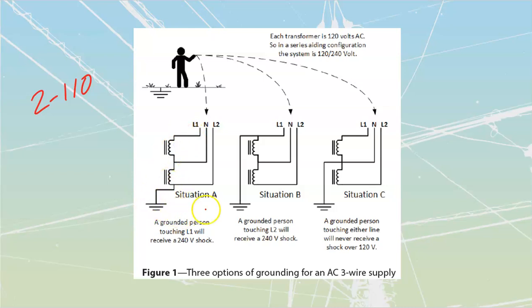So where we would ground the system would make a difference. This one over here, we would see that line 2 would be at 0 volts. They could touch line 2 safely, but if they touched the neutral, that would be 120 volts above it. If they touched line 1, that would be 240 volts above it. So there's danger over there, right? That 240 volt shock. Same with this one. If we grounded the other line, we would be able to get 240 off of that line, just standing still with our human at ground potential over there.